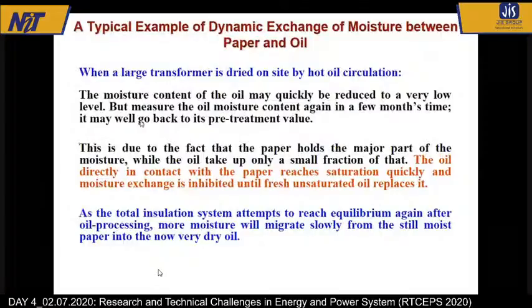Now, this I have explained right. Now, two things have been experienced in life. There was a case when, in a transformer, the oil moisture was found high. So the company decided that we'll change the oil. Before the change, it came down to a few parts per million. After 1 month, they thought that we'll test again. And when they tested, immediately it was 16 parts per million.